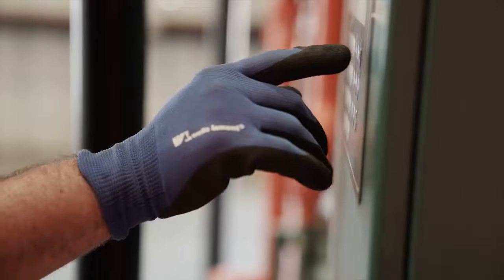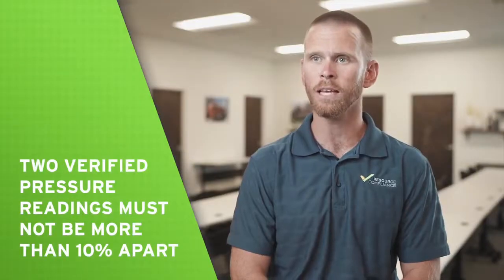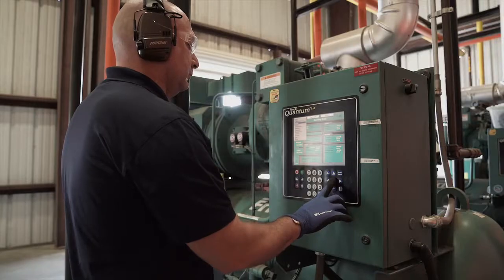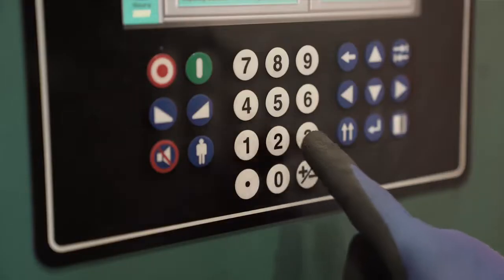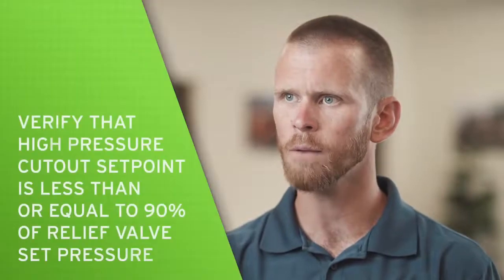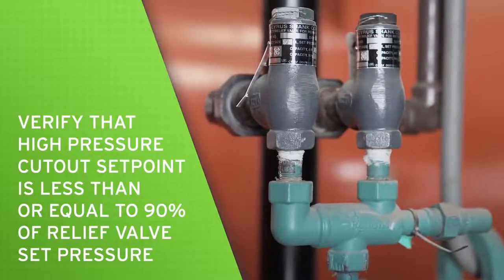IIAR Standard 6 recommends that the transducer be verified at two pressures that are not more than 10% apart. A successful test will de-energize the compressor, but it is important that trained personnel be available to restart the equipment after completing the test. Before testing a high pressure cutout, make sure to notify facility management if the test will be taking place. Once approved, verify that the high pressure cutout setpoint does not exceed 90% of the compressor relief valve set pressure.